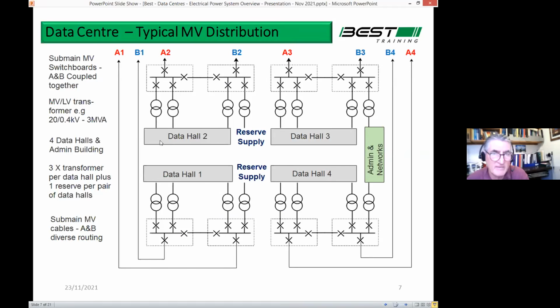This is showing a data center with 4 data halls, and each data hall has 3 transformers feeding it. You can see data hall 2 there on the top has 3 transformers feeding into it. Each of those transformers is typically something around 3 MVA, 3 megawatts. So that means there's 9 megawatts of power going into that data hall.